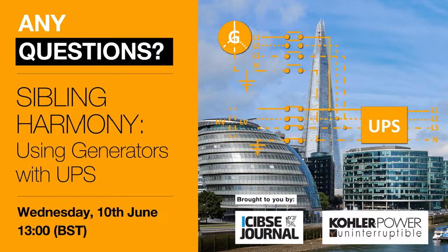But as far as using modular onto generators, it does help that we can step in the load very, very well when we put a modular UPS onto a generator, although we do have a lot of standalone UPSs running on generators as well, with absolutely no problem. But we just have to understand the installation, what the step loads are, and therefore we can size everything accordingly. Okay, thanks. And DRUPS, of course, stands for Diesel Rotary Uninterruptible Power Supply. People can look that up later on.